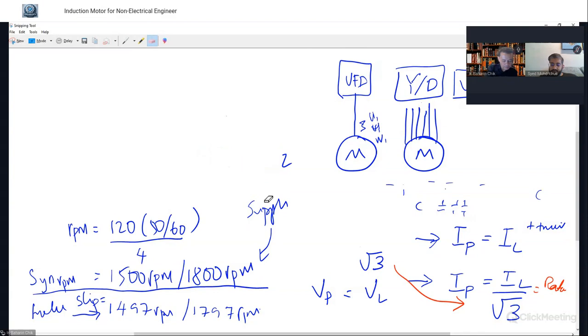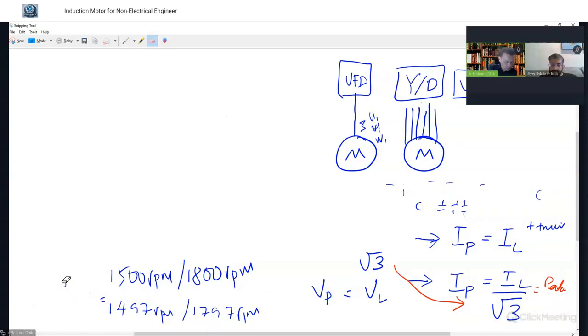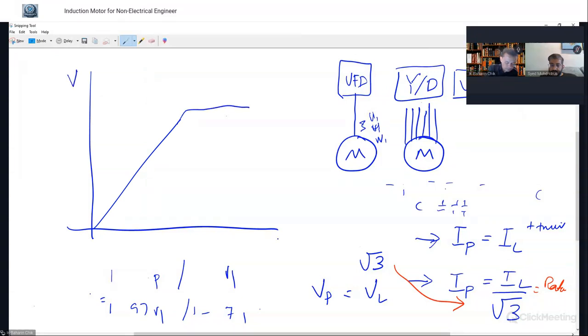What I understand, this is related to the mechanical limitation. What I understand is the VFD works on the principle of V over F. The limitation that the VFD has is actually the voltage here. For example, this is the voltage for the motors, let's say 11 kV. Now the frequency can go higher. I think in API or something, I can't remember, at least 5% running over the frequency. That means this is a linear V over F.